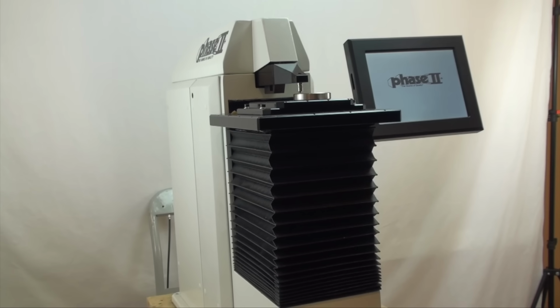This is an instructional video detailing the applications and functions of the Phase 2 Twin Rockwell Superficial Rockwell Hardness Tester with automatic Z-axis. These Dolphin Nose Hardness Testers are designed to test primarily metals using the Rockwell Hardness Method via a closed-loop, load-cell-driven control. This replaces the older weight-loaded systems where the testing performance was not as consistent or as accurate as the current load-cell system.